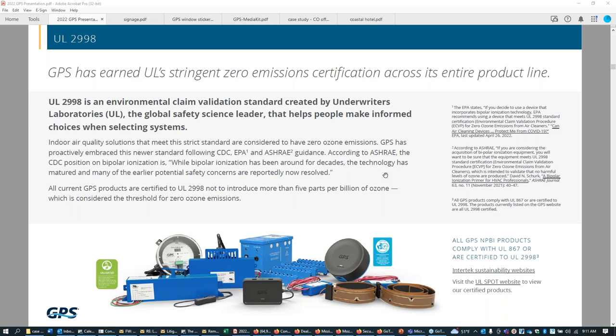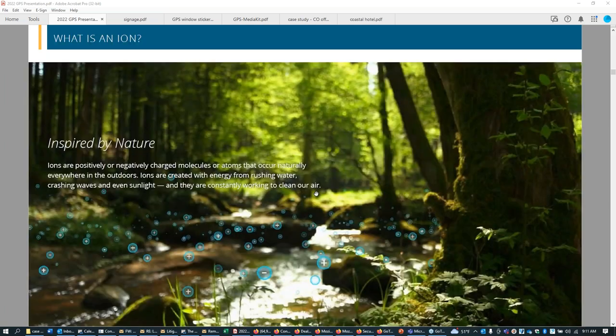So the entire product line at GPS carries this UL 2998 credential. And that means they consider that no ozone generation. And when you don't generate ozone, then you don't generate the byproducts that are associated with some of the concerns related to ozone. Not to mention, ozone is a great disinfectant, but it is also an irritant for the lungs. So CDC and ASHRAE both say, if you're going to apply an electronic air cleaner, make sure and look for that UL credential to make sure that you're not introducing ozone to your space.